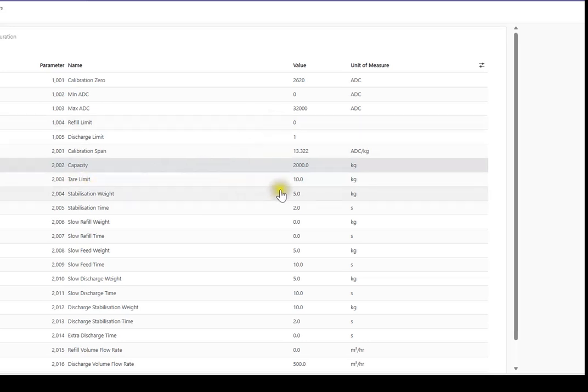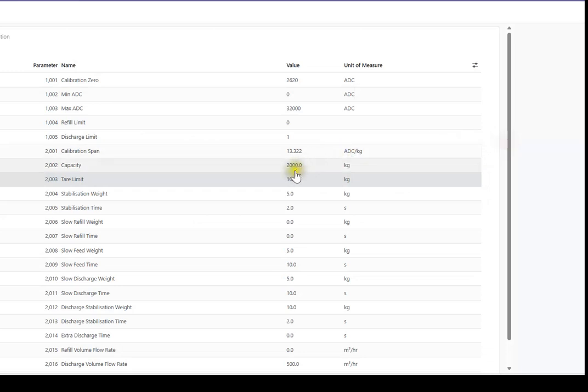The tare limit is set to 10, so that if the weight, before it starts, is more than 10 kilos or less than minus 10 kilos, it will stop and alarm to say the scale is out of tare. The stabilization weight: when the weigher finishes feeding, it stabilizes for 2 seconds as long as the weight hasn't gone up by another 5 kilos. And the same thing for slow feed. If it's feeding and it doesn't go up by 5 kgs in 10 seconds, then it will alarm.